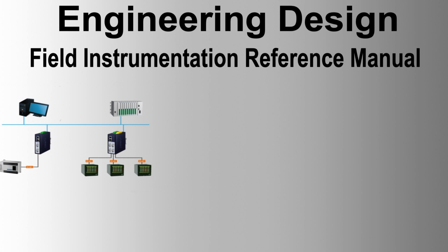General installation notes. Inline instruments such as inline flow meters, control valves, orifice plates, strainers, and heavy offline equipment, such as displacer-level instruments and tank gauges, should be installed by the mechanical engineering discipline under the supervision of the instrument engineering discipline.